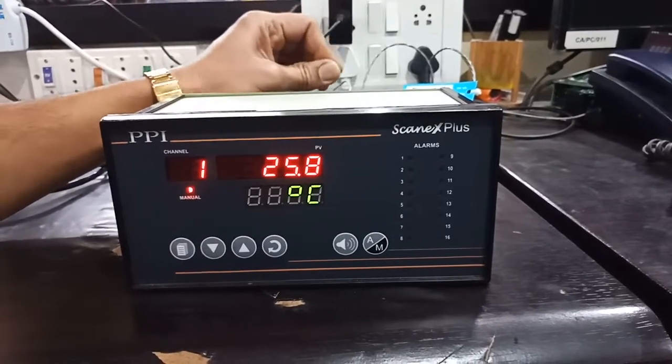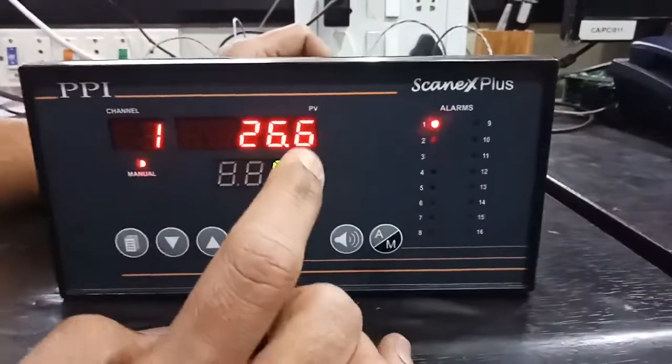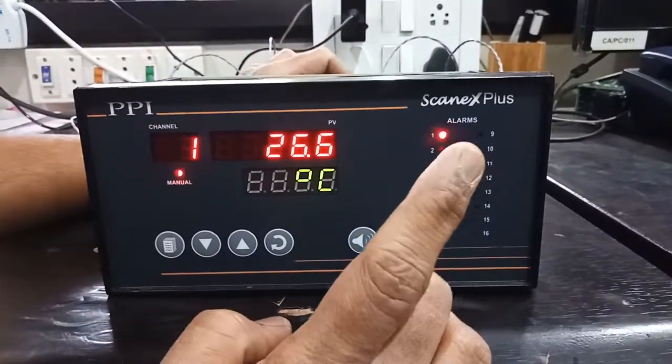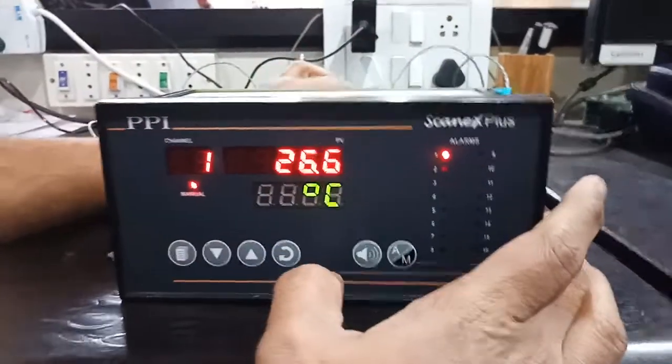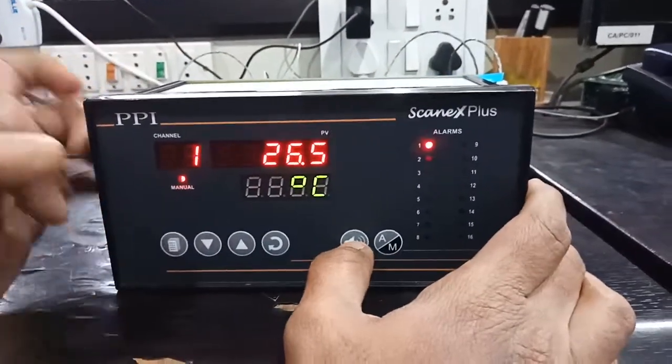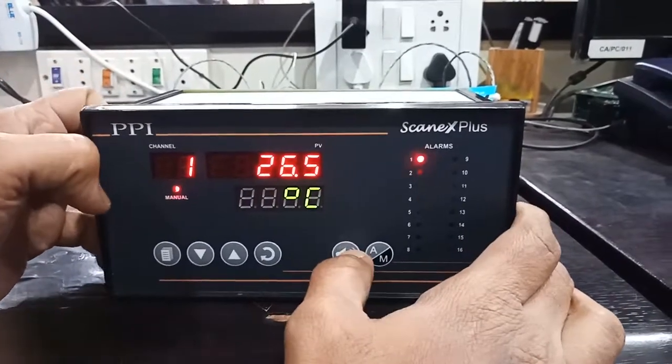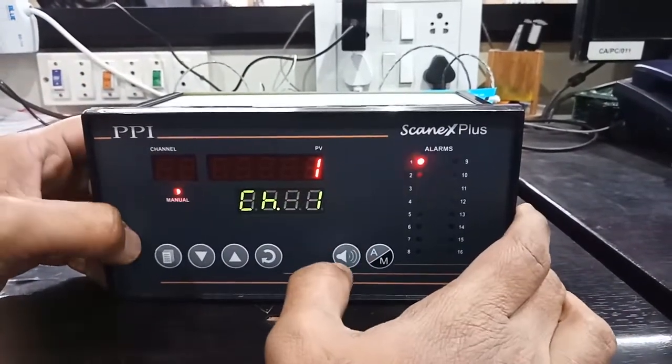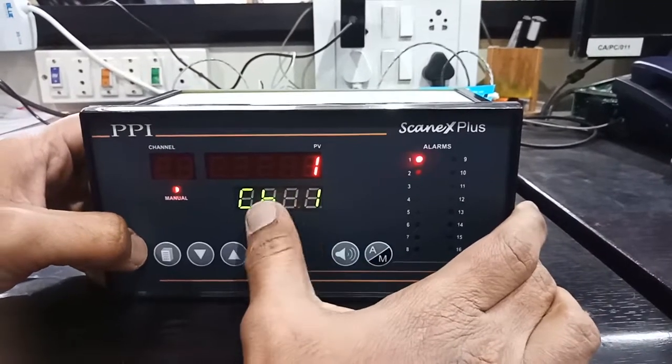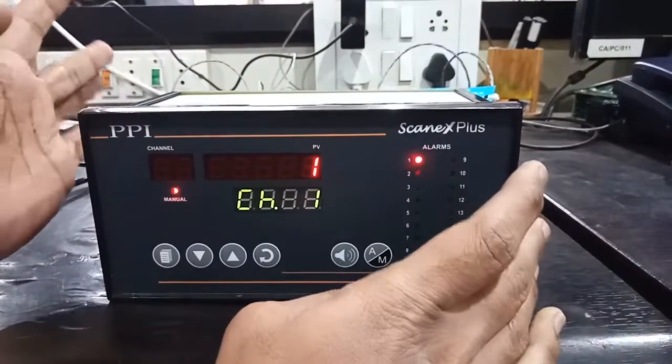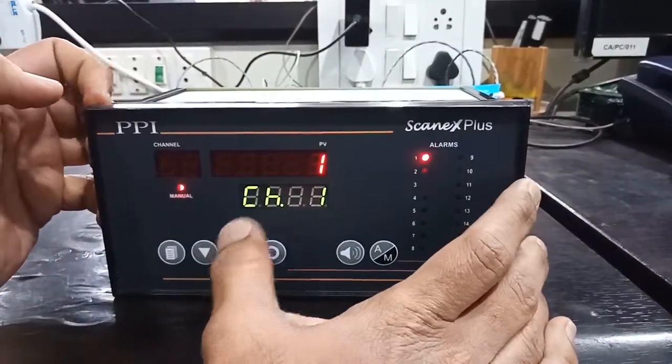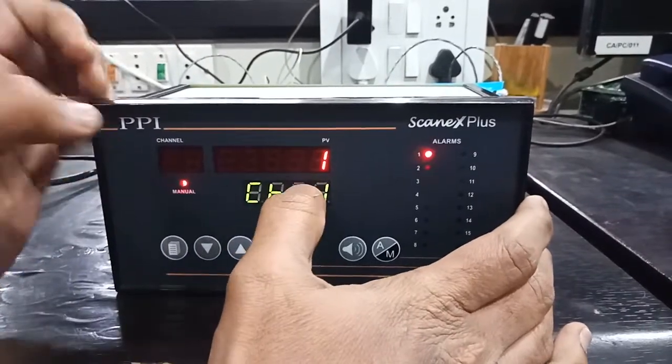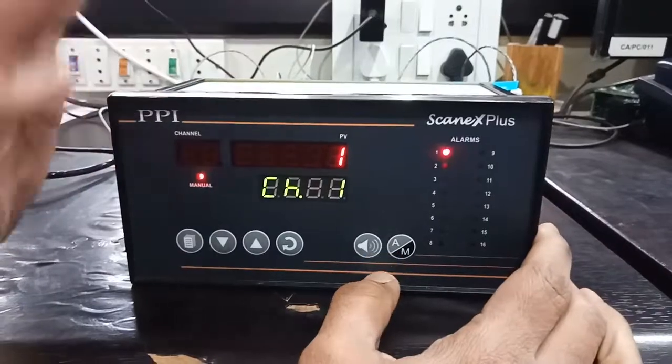I am increasing the PV value, and once it is above 26 degrees, the alarm LED turns on and it will show you the alarm indication. You can check which alarm is running and the alarm status on the PV value on the main screen by pressing the acknowledge button. You can see channel 1 alarm 1. If many numbers of alarms are there for different channels, you can scroll by pressing up and down arrow keys. It will show you the different channel values and number of alarms that are on.